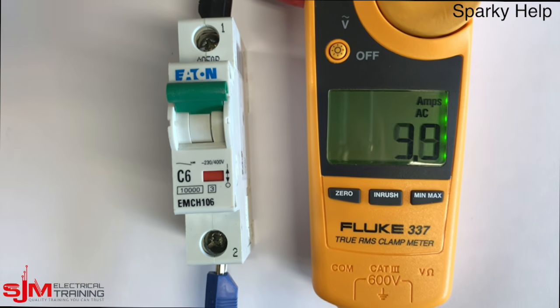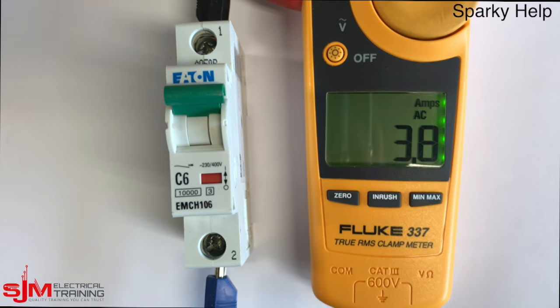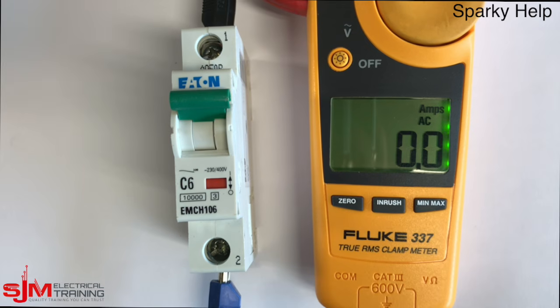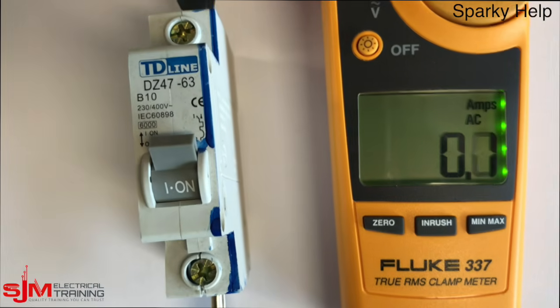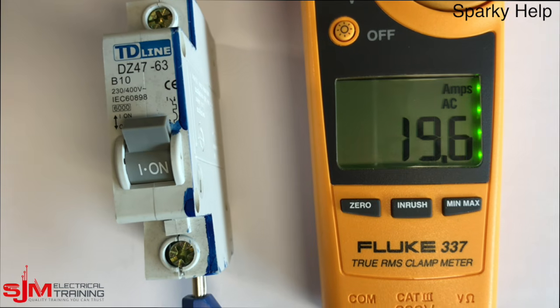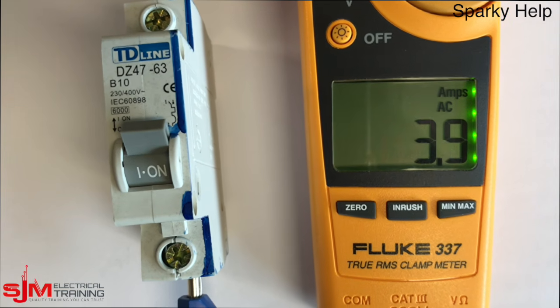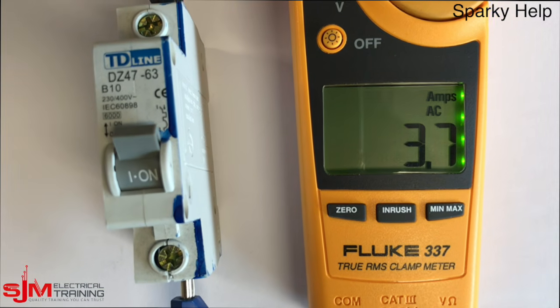So it can withstand the inrush because it's not going to go just yet, and it quite happily runs at the running current. Obviously in some cases what the manufacturer will do is they won't say put a Type C, and they might say go up a size but keep it a Type B. So here we have a 10 amp Type B, and this will also stay on, but always be guided by what the manufacturers state, because they are the ones you should follow.